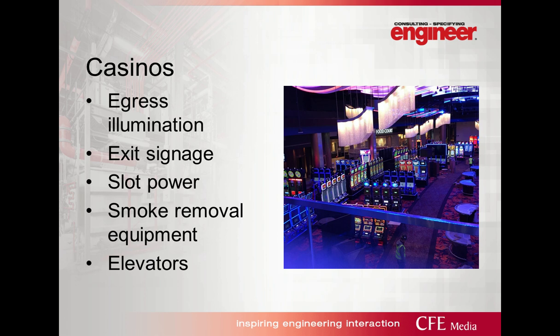The first item that I wanted to bring up, because I'm most familiar with it, is casinos. I've highlighted some of the items that are typically seen for casinos as far as, I'll say, generator power, because one of the concerns that I always have with the different players involved in the design of facilities, whether it be a casino or an educational facility, is that everybody looks at the word emergency differently. And for us, emergency power for this type of facility is determined by Article 700 in the National Electrical Code, in conjunction with the other codes that Rich had mentioned, such as NFPA 110.